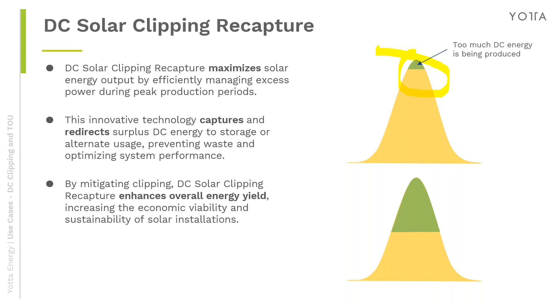So if the module is, let's say, 750 watts, and the inverter is only capable of putting out 450 watts, we can store that excess power in the battery and make sure we're pumping out 450 watts from the battery to maximize the power output. What we would typically have lost now gets stored in the battery and used for later.